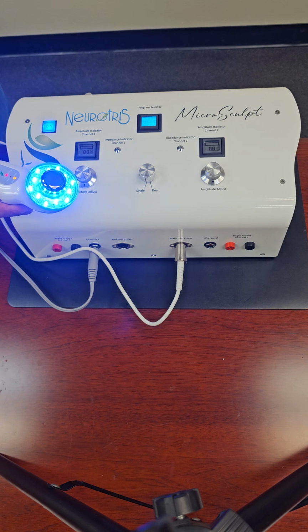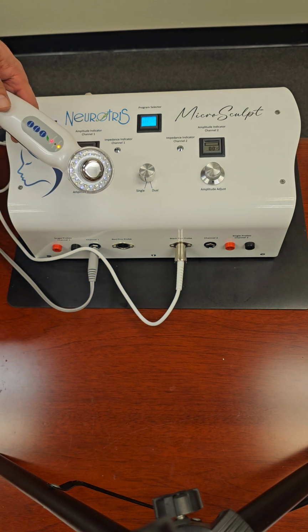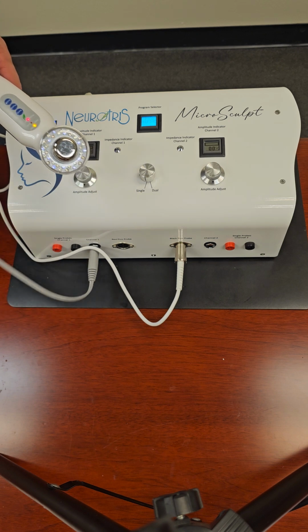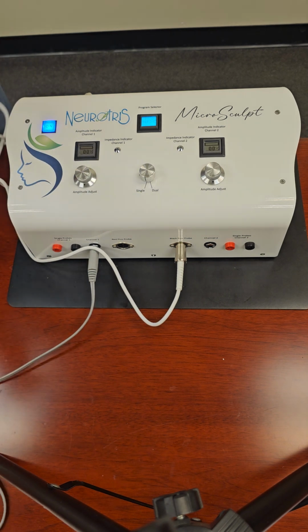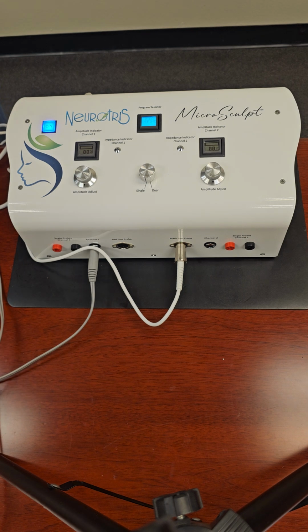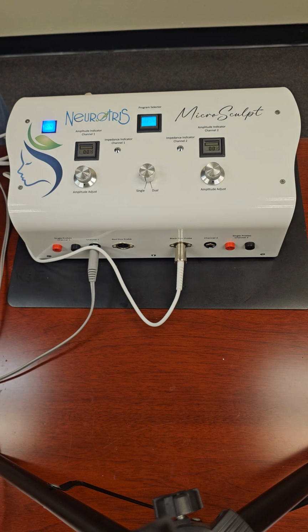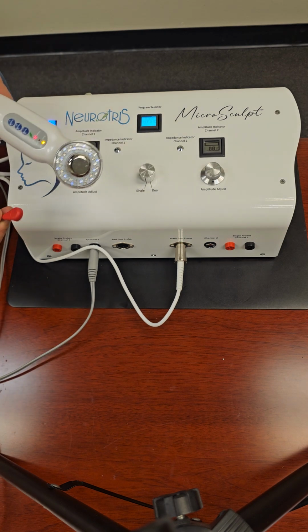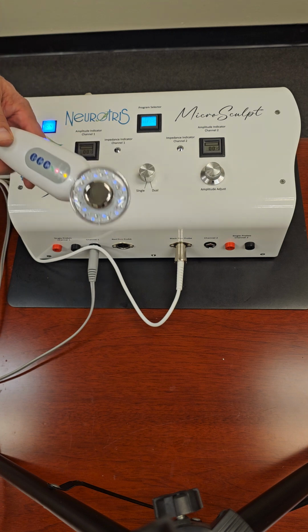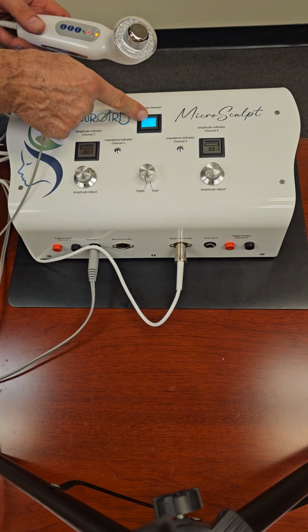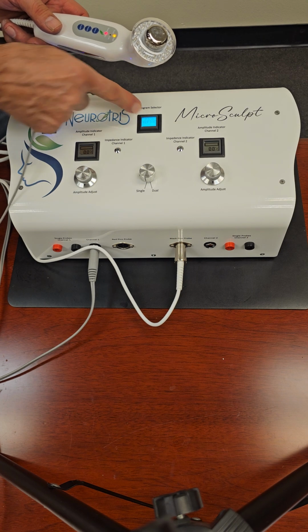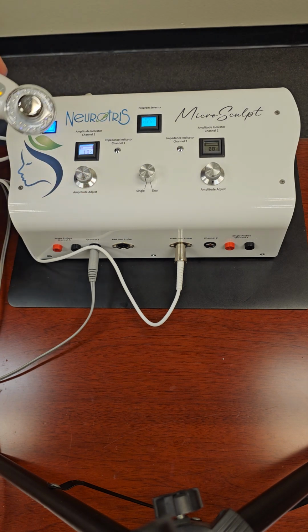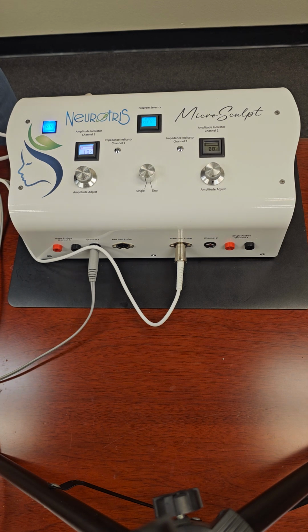So you can have the sonic going, and you can have the LED going at the same time. But if you want to use the microcurrent, okay, it's very important that you complete the electrical circuit. So you're going to need to connect the red to either a body pad and put it onto the client's body, and then you could use the microcurrent by selecting the microcurrent on the machine, and it'll run through. You can set your settings, and of course the light will come on when you have it on the skin and the microcurrent's working. That will indicate that it is on. Okay, so when I put the pad on the skin, there we go.